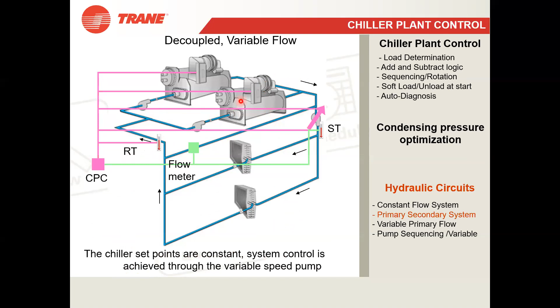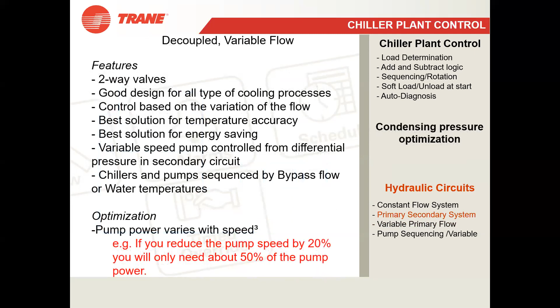But the main point is what? Pump power varies with speed to the power 3. So you have reduced your speed by 20%. So just think of 20% to the power 3. How will it be reduced? It will be more than even 50% actually. This is just a calculation. So a 20% speed reduction will need about 50% of the pump power, nothing more. So by doing this, you are actually saving a lot.